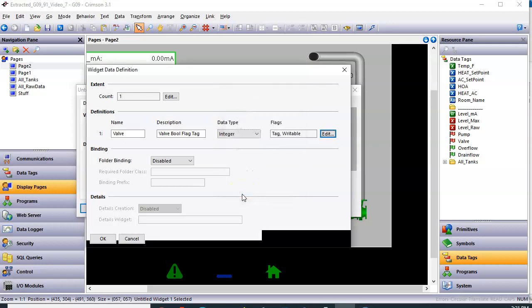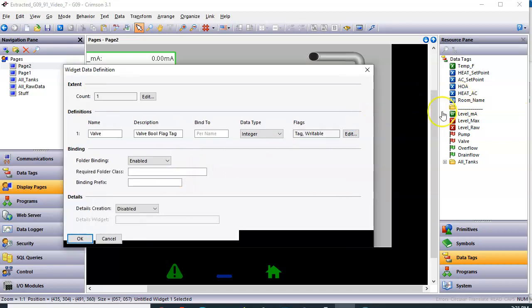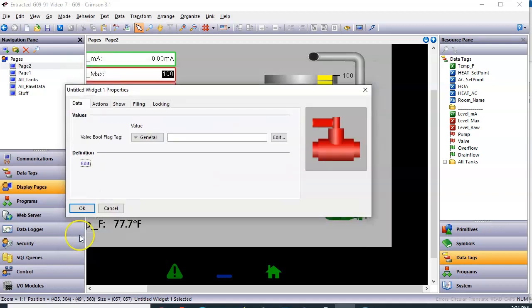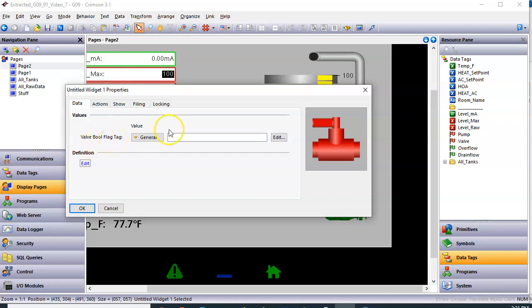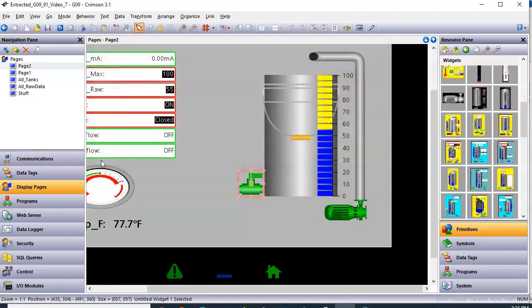And then the last part is the folder binding. I'm doing this to make that graphic get disconnected from this guy, and it gets connected to this tag which resides in the graphic. So I'm going to turn on folder binding. Go ahead and click the OK button, which brings back here. There's that description I was talking about, Valve Bool Flag Tag. Once again, I'm going to click the OK button. And let's see if this guy changes. It turned to the on state. Interesting. So now that I got this state right here, I'm going to go to the organize pull down, save widget.